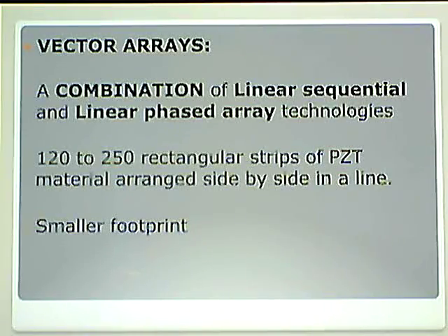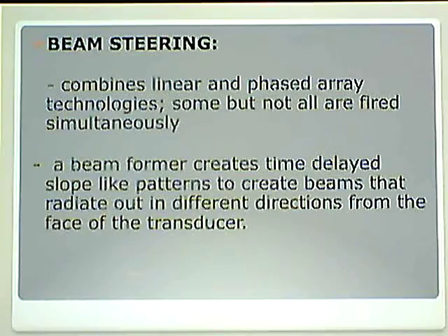So all we're doing is talking about an idea that instead of just having that rectangular shape, how do we see out to the sides? How do we get wider than the linear sequential array transducers? How do we get outside of that rectangle that might be only 10 centimeters long? How do we see past that? So again, it's a combination of linear sequential and linear phased array technologies. They're rectangular strips of PZT material arranged side by side in a line, smaller footprint. The beam steering combines linear and phased array technologies, but some, not all, are fired simultaneously.